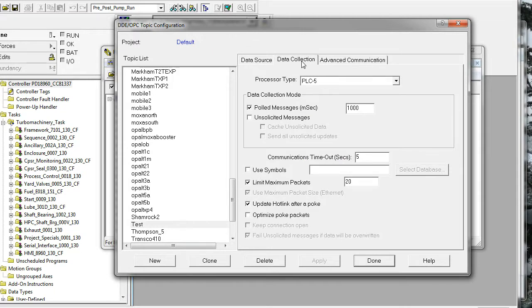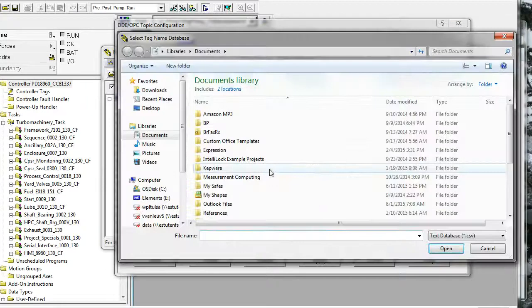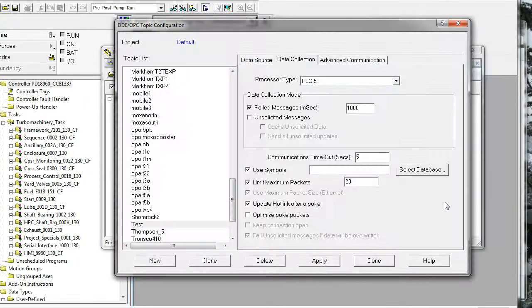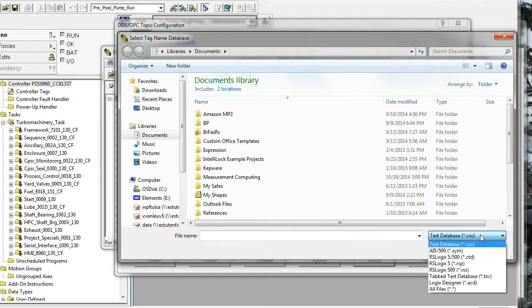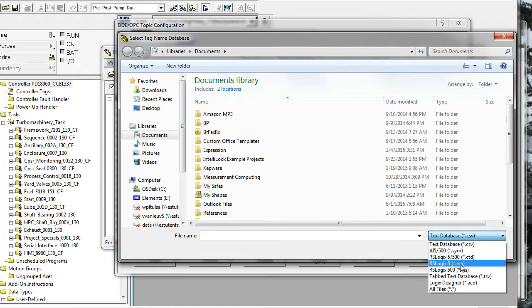Under the data collection tab, click on 'Use Symbols.' It offers different formats for the tag list. If you have a PLC5, you will want to save your RSLogix 5 file as a .RSP — open the logic file and save as .RSP. If you have a ControlLogix project, all you have to do is browse for the ACD file. No export is required; you can use the logic file directly.